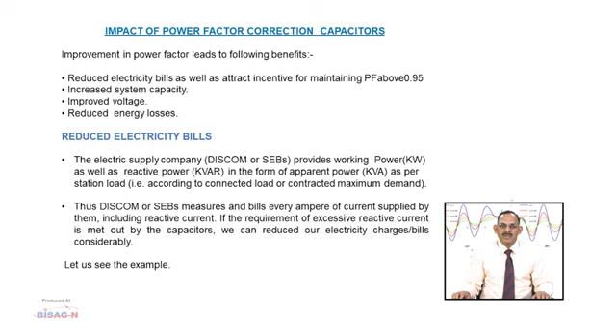Thus, distribution companies or state electricity boards measure and bill every ampere of current supplied by them, including reactive current. If the requirement of excessive reactive current is met by the capacitor, we can reduce our electricity bills considerably. Let me see the example. Let the maximum demand of a station be 500 kVA. Existing power factor is 0.87, which is normally good. The rate per kVA is rupees 10. The power factor is improved from 0.87 to 0.95.